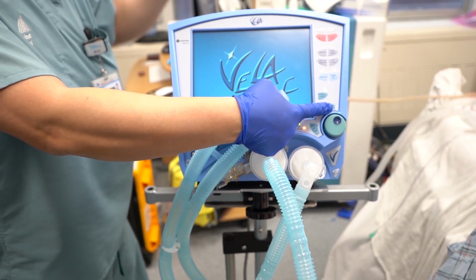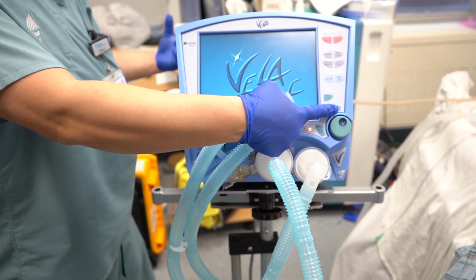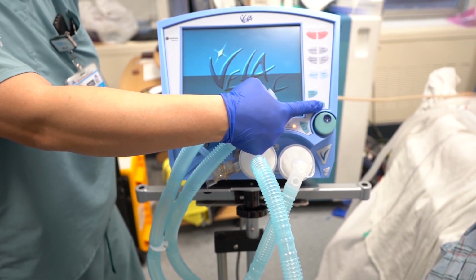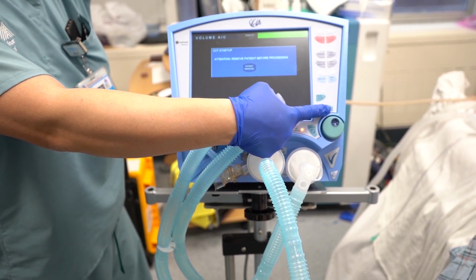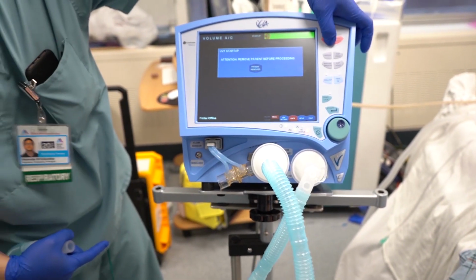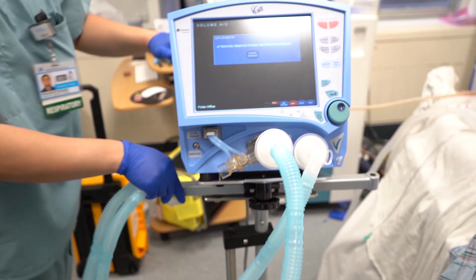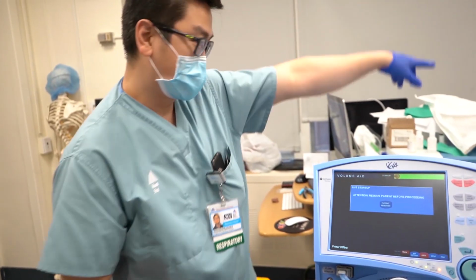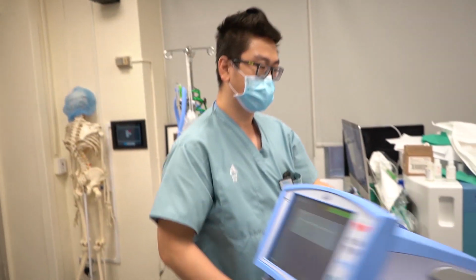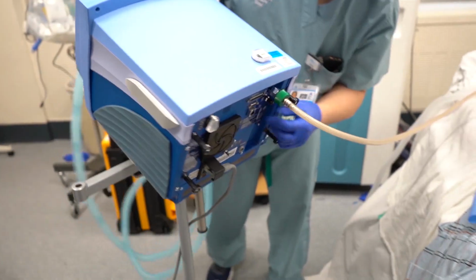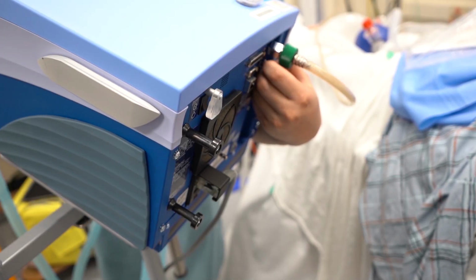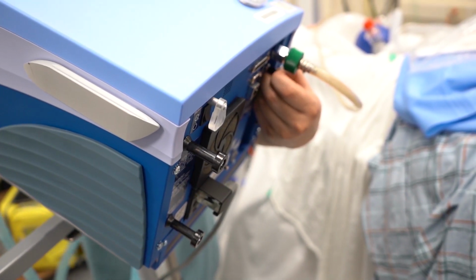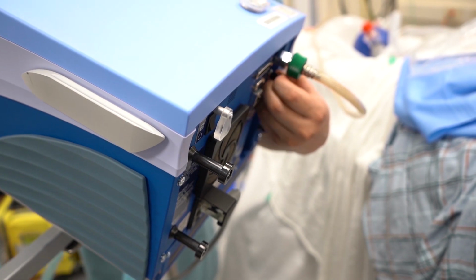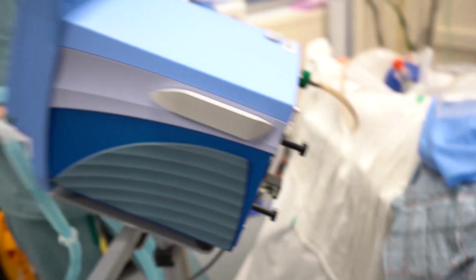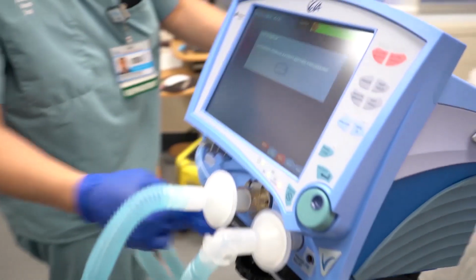So on the inside it has a turbine compressor which sucks in the air, so you're only going to need an O2 gas source. If there is no oxygen source, you can also do a bleed in through this nipple adapter on the back. Then you can run however many liters of oxygen through a flow meter, run it through here, and it'll mix with the blender on the inside of the machine.